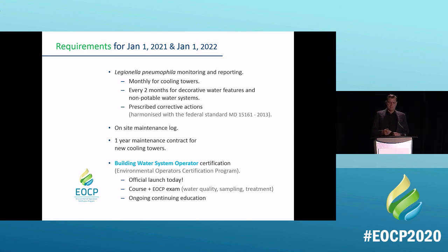For decorative water features and non-potable systems such as rainwater harvesting, it's every 2 months. Rainwater harvesting already requires water quality testing every 3 months for E. coli, temperature, and turbidity. On top of that, as of January 1st, 2021, it's going to include Legionella as well, and cooling towers will start monthly testing.